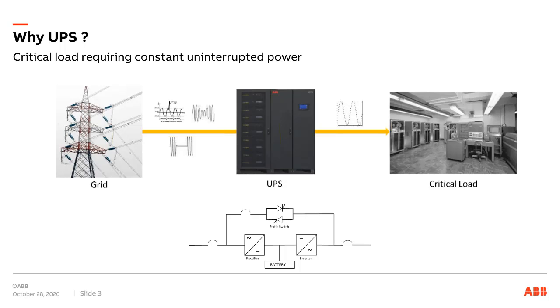The uninterrupted part comes in that there's an energy storage, a battery connected to the UPS, so the UPS can take power from the utility or it can take power from the battery. So the main components in a UPS is, like we see at the bottom of the slide, single line of what we know as a double conversion online UPS system, where the mode of operation is that the power is coming in from the left from the utility to the rectifier. The rectifier is rectifying that from the AC to a DC and feeding that DC to the inverter.